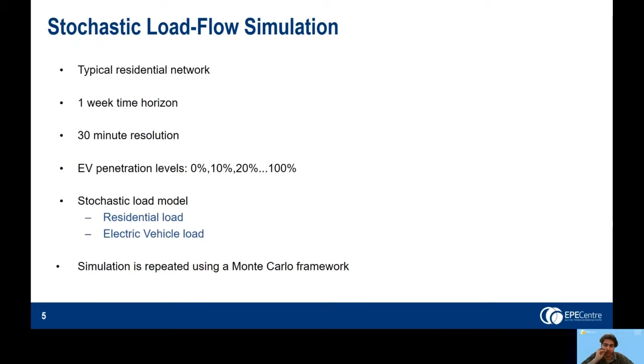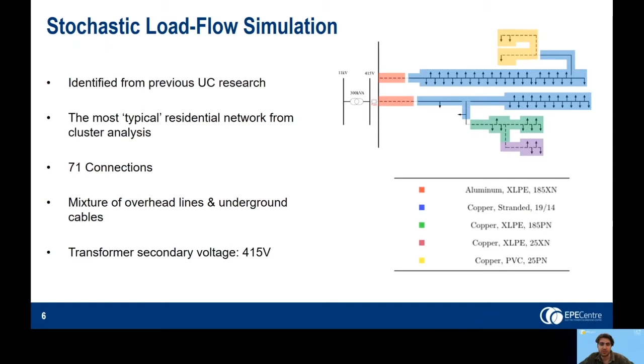The figure on the right here shows the topology of the network which was modelled. This network was identified from previous research at the University of Canterbury and provides a highly typical residential network. It has a total of 71 connections and contains a mixture of overhead lines and underground cables. These are indicated in solid and dashed lines respectively. The different colours represent different conductor types, as indicated by the legend below the network there. For some reason the shades are a little bit off, but hopefully you should still be able to identify the different conductor types there. Finally, the transformer provides a secondary voltage of 415 volts, which is of course a little higher than 1 per unit.